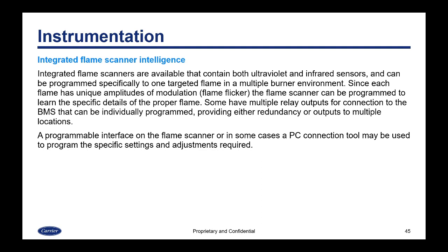Integrated flame scanners are also available that contain both ultraviolet and infrared sensors and can be programmed specifically to one targeted flame in a multiple burner environment. Since each flame has unique amplitudes of modulation or flame flicker, the flame scanner can be programmed to learn the specific details of the proper flame. Some have multiple relay outputs for connections to the BMS that can be individually programmed to provide either redundancy or outputs to multiple locations. A programmable interface on the flame scanner or a PC connection tool may be used to program the specific settings and adjustments you need.